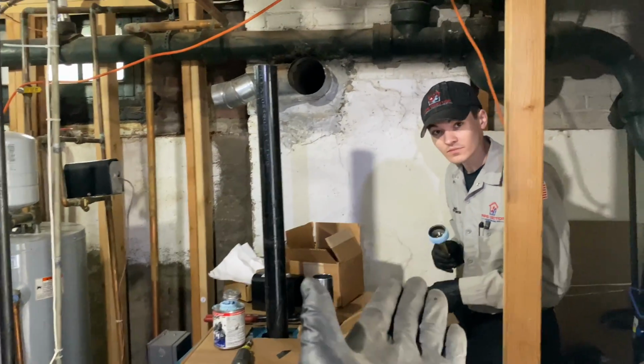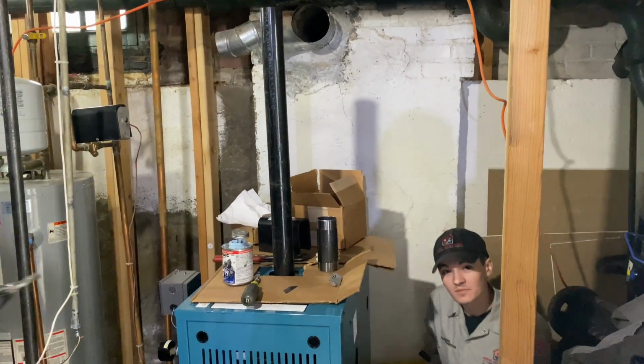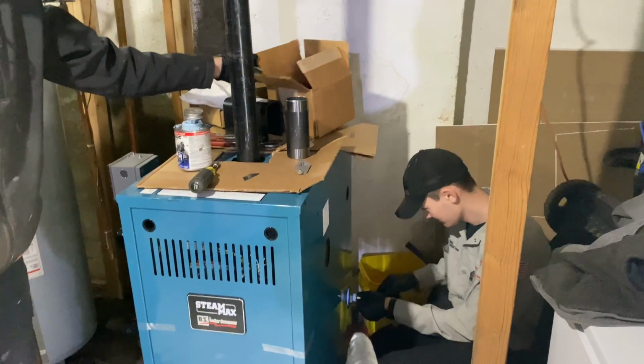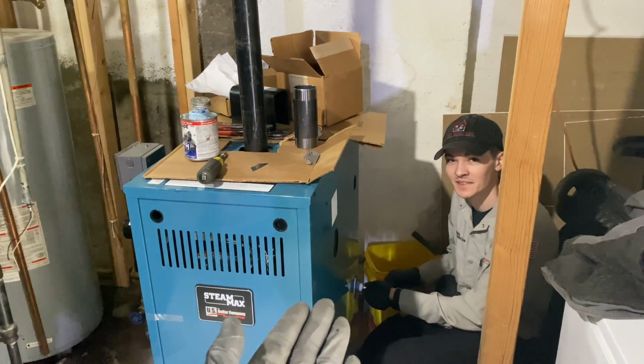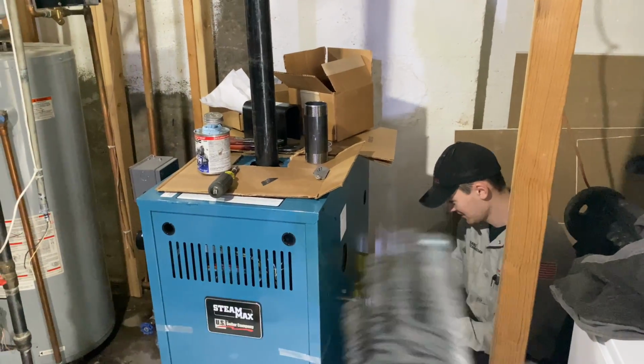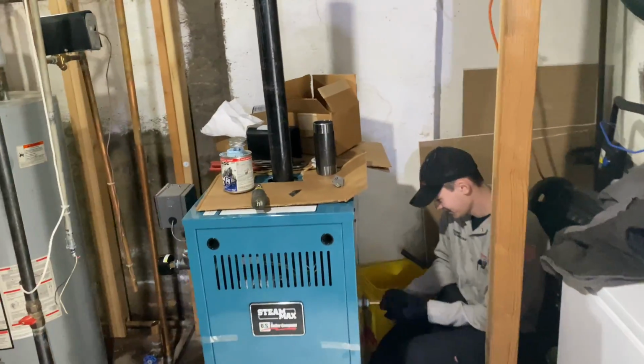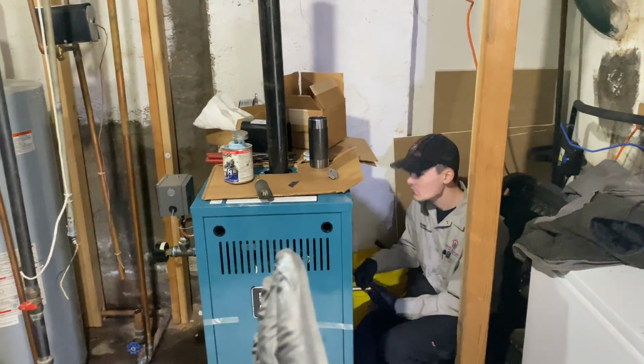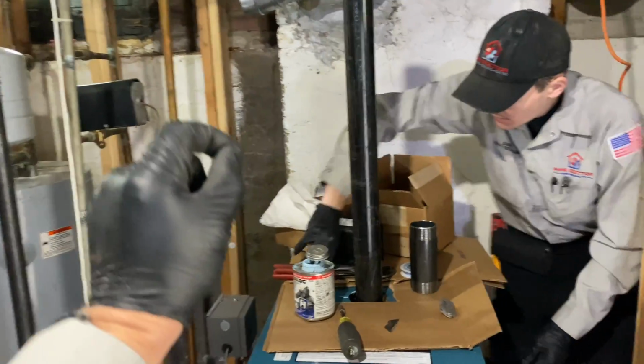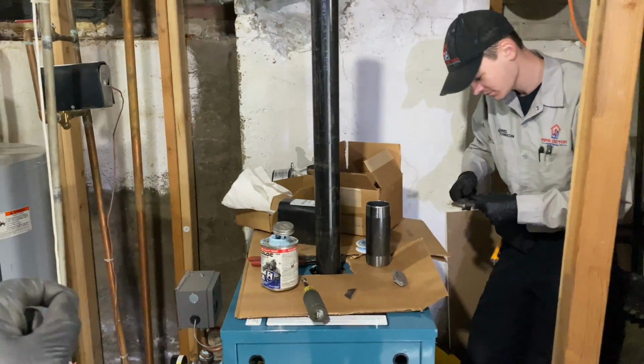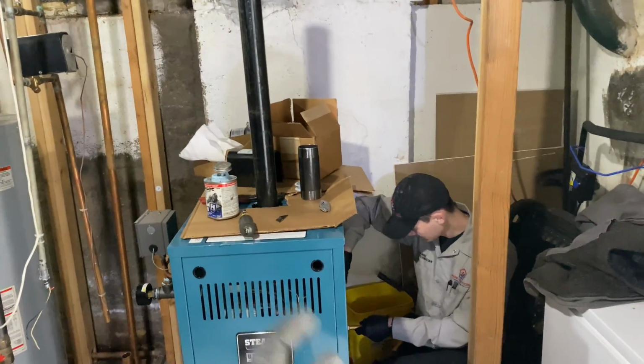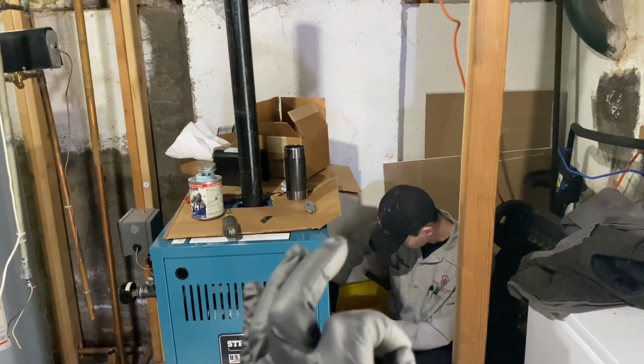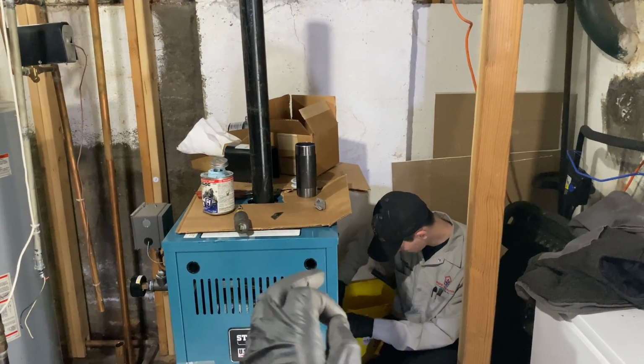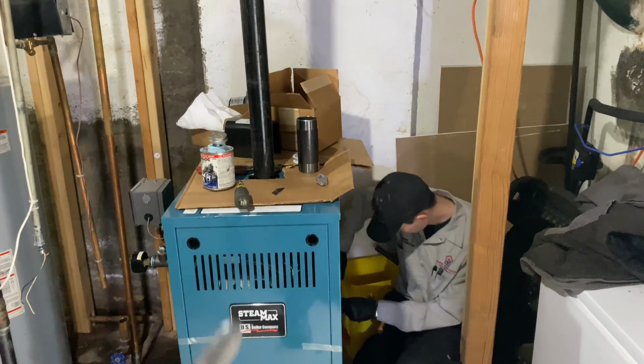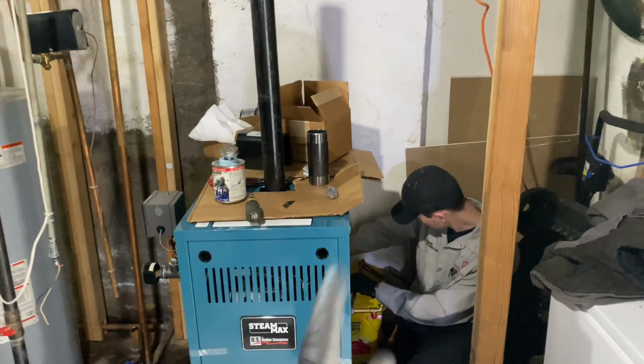Now that's great for homeowners, but as a professional, he also encouraged using a digital manometer to adjust your gas pressure to as low as 1.3 inches of water column on gas-fired equipment, as long as the state specifies that in the range. That's neither here nor there. You can use a digital manometer, hook it up to the tubing before it goes into the pressure switch off of the inducer assembly, and with the furnace off, turn the fan on. If you see any pressure increase on that digital manometer, you have a cracked heat exchanger, and it needs to be immediately condemned and shut down.